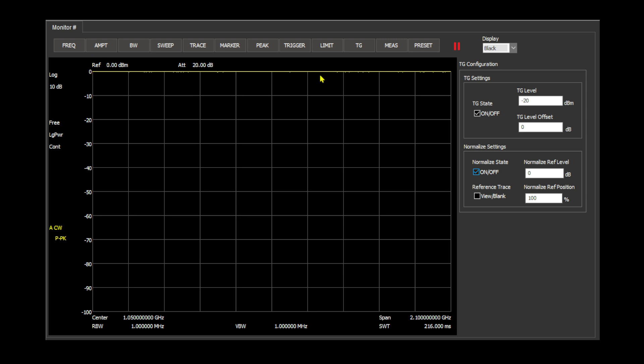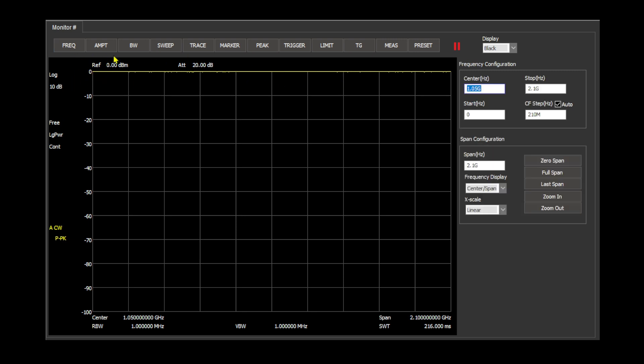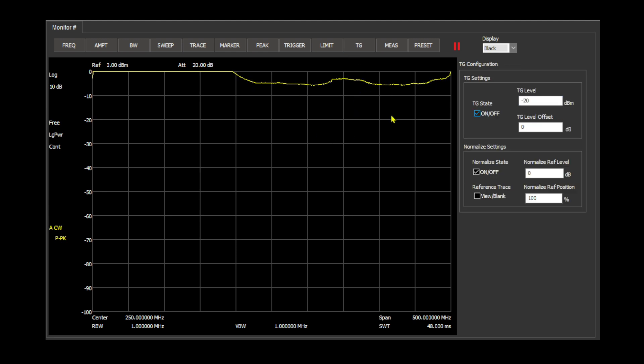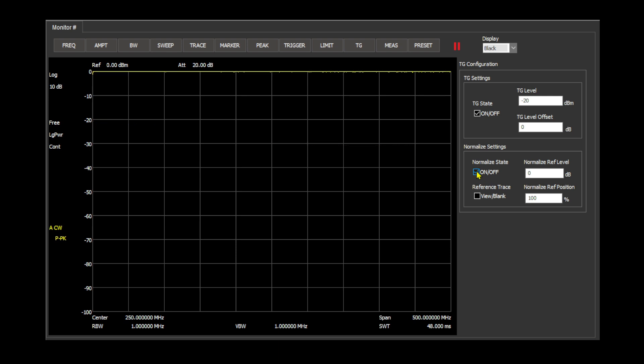The next thing I'm going to do is go over to my frequency, and I'm going to adjust my stop to 500 megahertz. And then look at that, I kind of messed that up a little bit. Let's go back to tracking generator and let's re-normalize. There we go. And we are good there. The reason that I'm only going to 500 megahertz is because I usually characterize these at HF, UHF, and VHF.